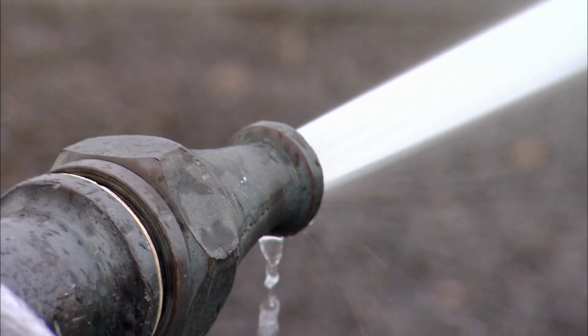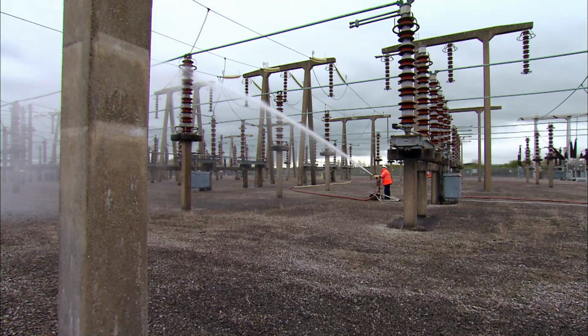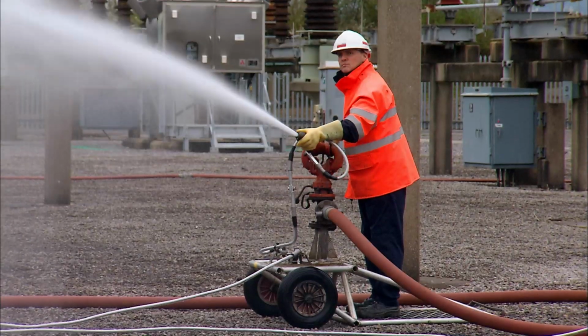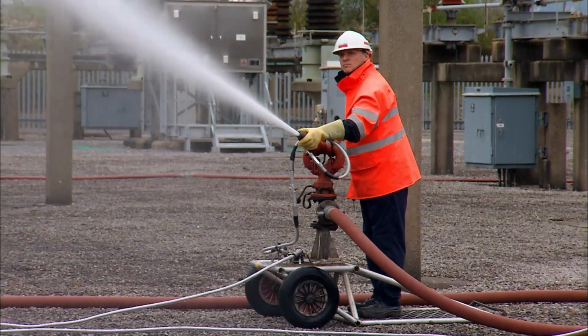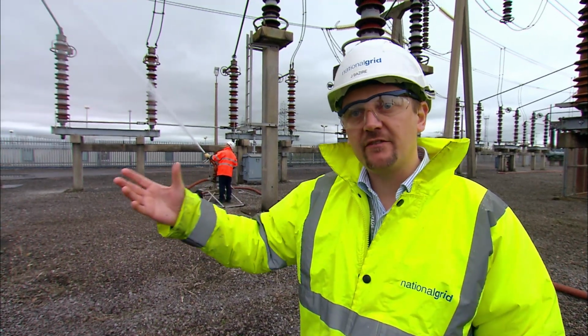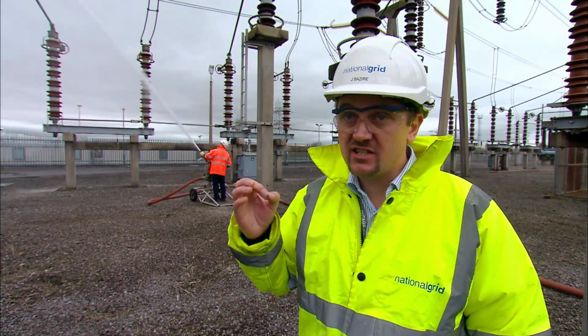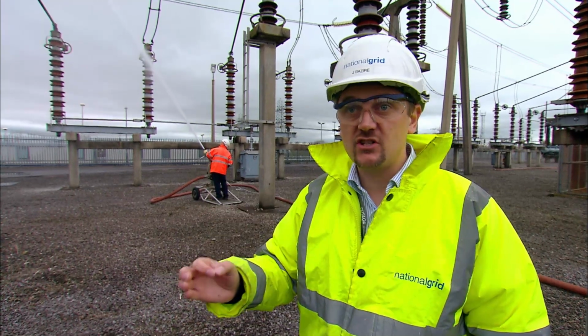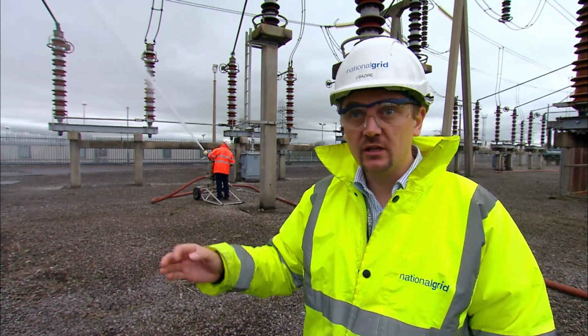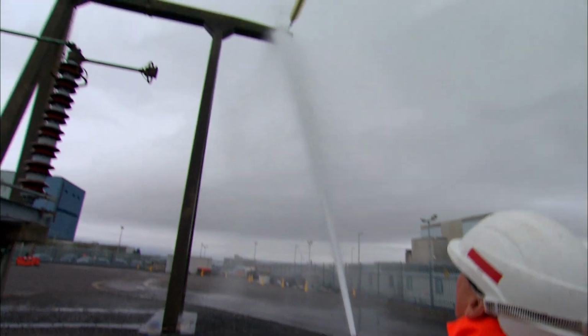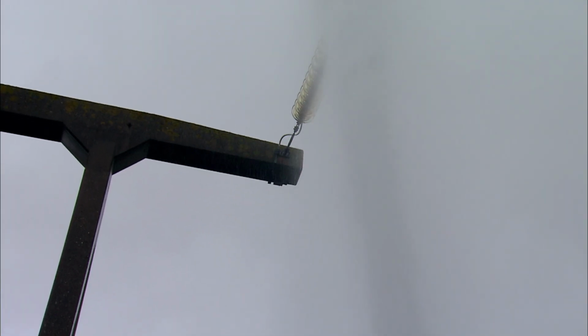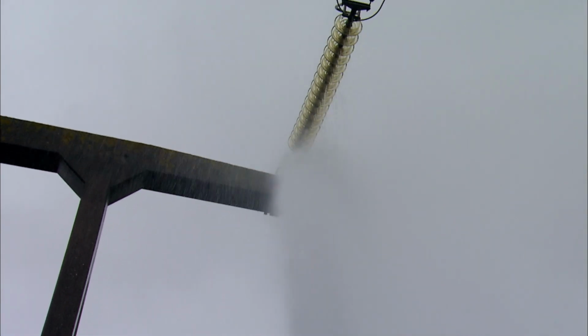With the water in separate droplets rather than a continuous jet, it's harder for electricity to track back to Pete. This prevents Pete from getting a flashover back to him. This is absolutely critical and part of the safety checks and monitoring that Pete has to do whilst he's washing. And then we're coming on to the earth end, and we're going on to the live end at 275,000 volts.